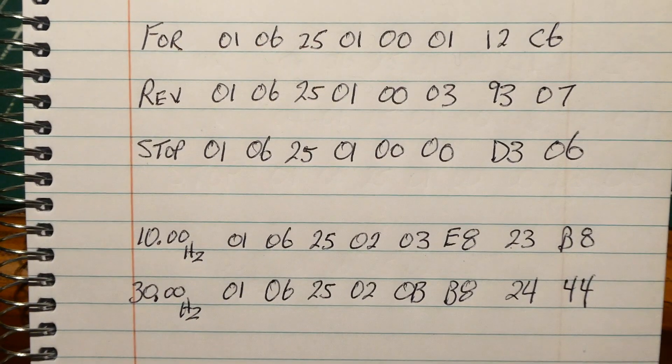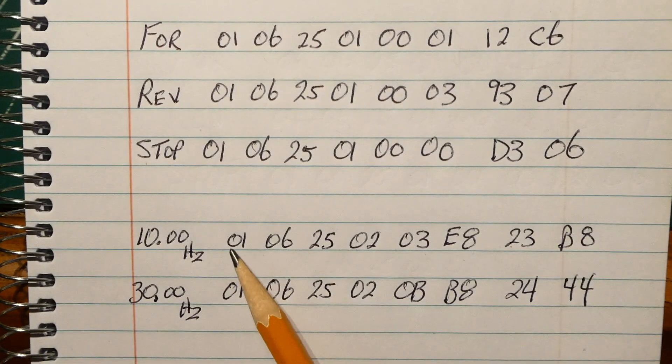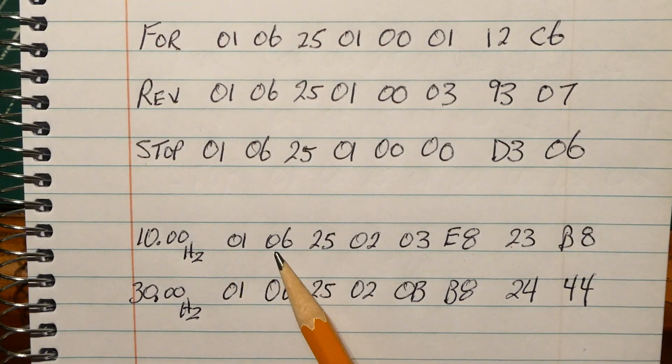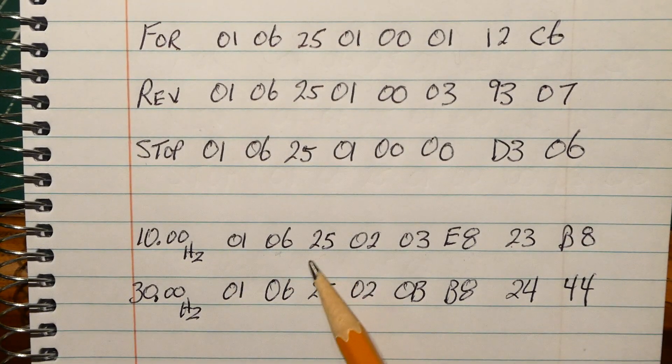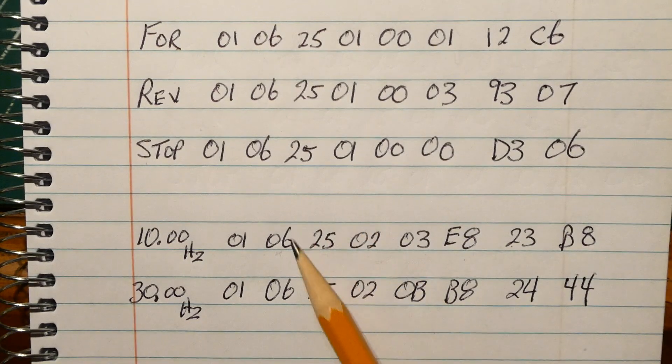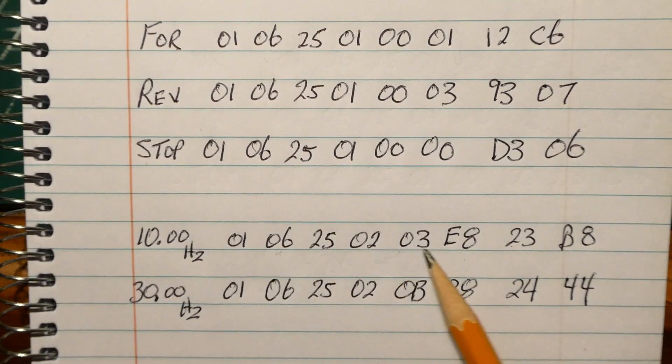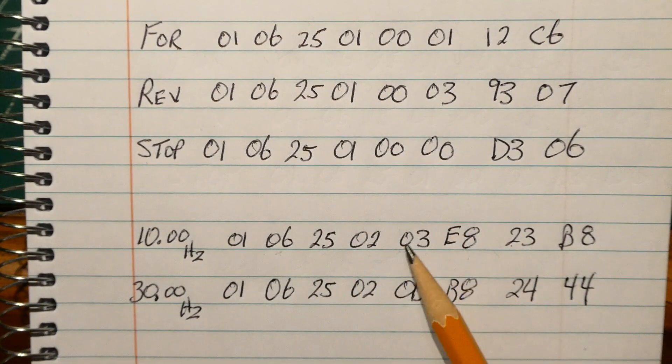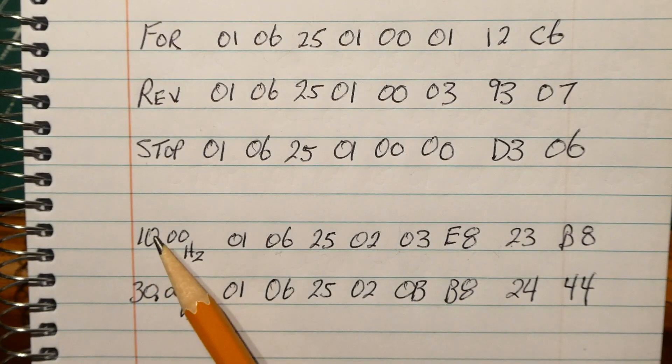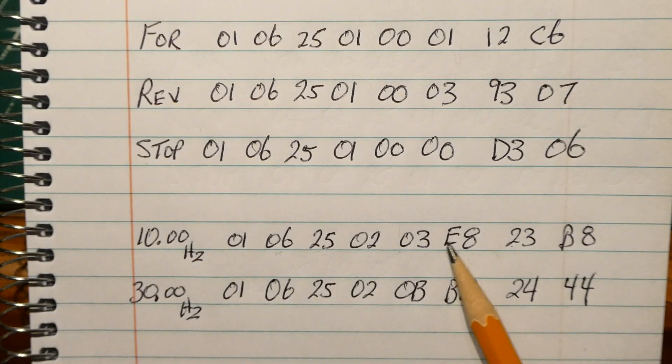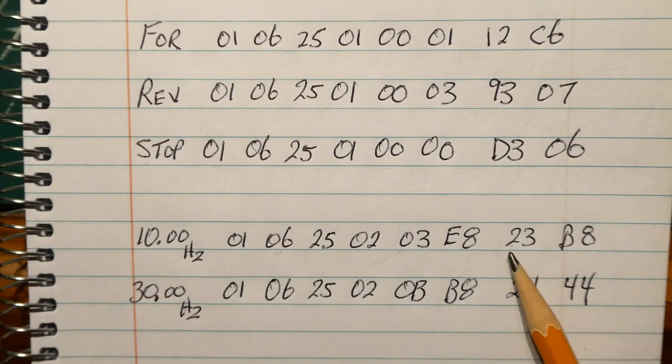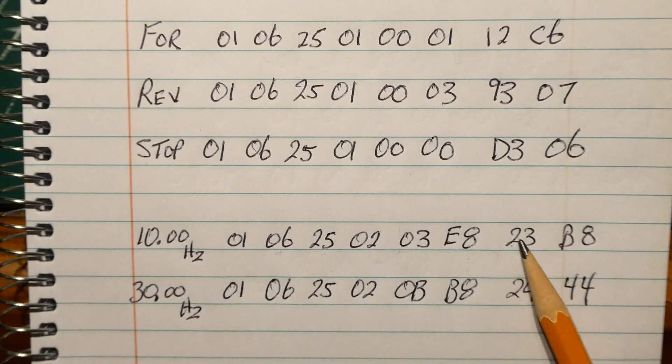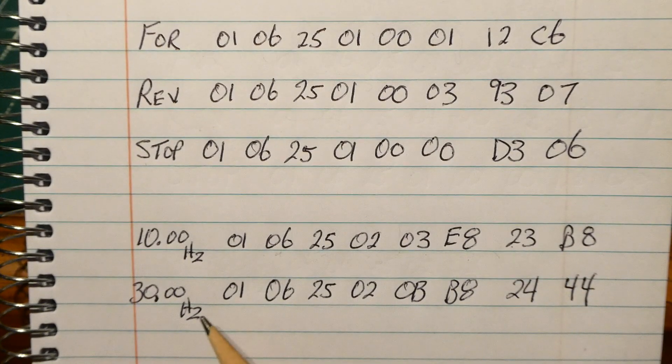Now for the speed, same sort of thing, 01 is the address, 06 we're doing a write, this time we're using this register, 2502 for the speed, and this is our speed command. So if we take 1000 decimal and change it to hex, we're going to get 03E8, and the last two bytes is our 16-bit CRC checksum.